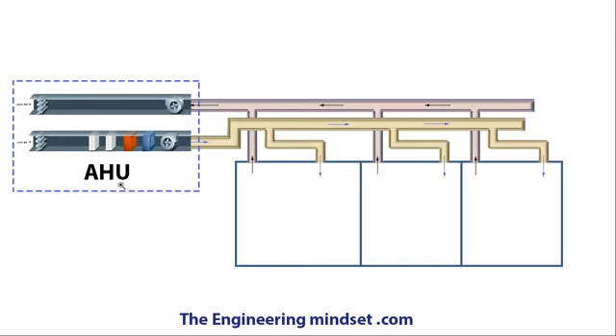Now in your AHU system, where you've got your supply AHU there and your discharge or extract AHU here, your filters are going to be before any of the heating or cooling coils and the fan, and should be just after the dampers. If you've got air recirculation happening in your AHU, where some of the discharge air is recirculated back into the fresh air intake AHU, then obviously your filters need to be downstream of this to filter all the air which is coming through and is going to recirculate into your building.